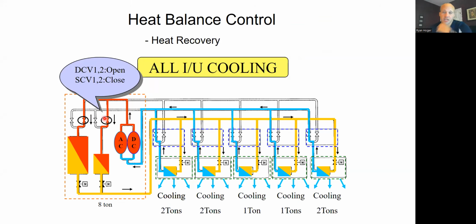All right, let's go through the heat recovery, heat reclaim operating scenarios. So I've got three different scenarios, maybe four, showing you here. In the red dotted line on the left is my outdoor equipment. My 5 indoor units are over here on the right in this case. I have a couple of condenser coils outside when they're in cooling mode and 5 evaporator coils inside when they're in cooling mode. I have an 8-ton unit, with 1, 2, 3, 4, 5, 6, 7, 8 tons in this case, so it matches up evenly.